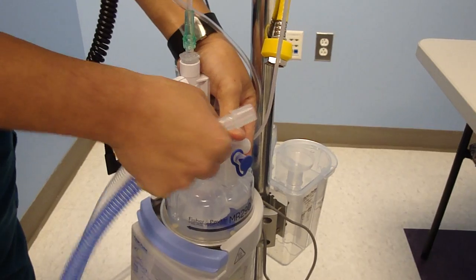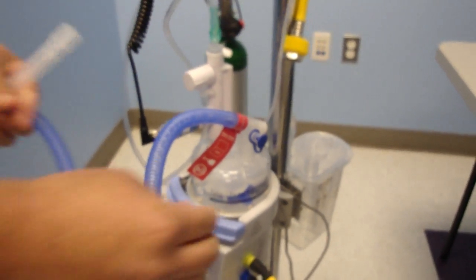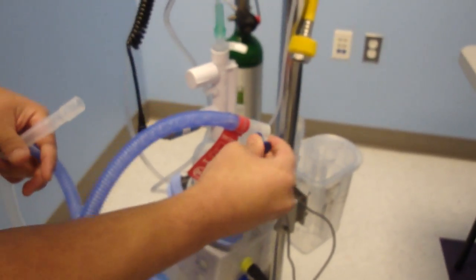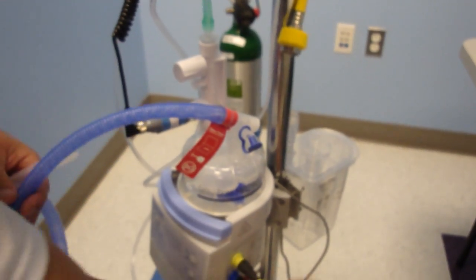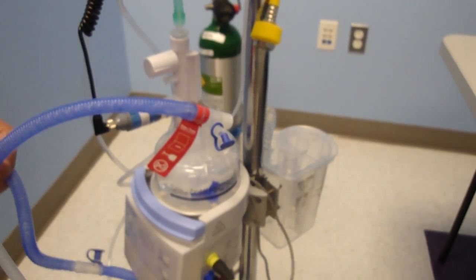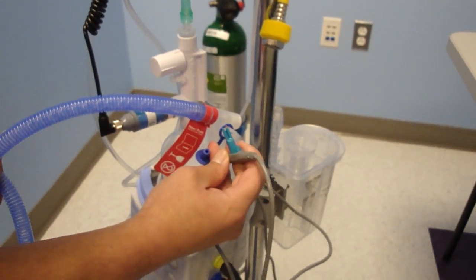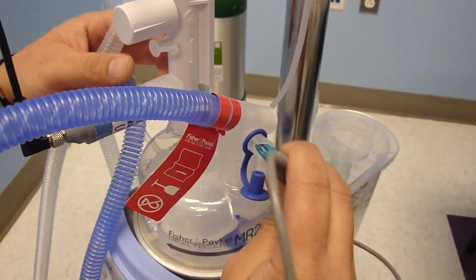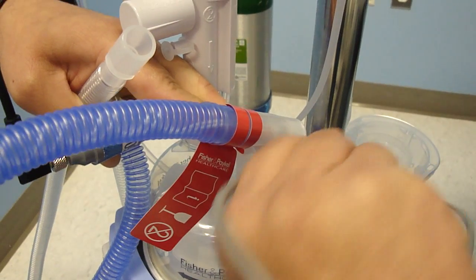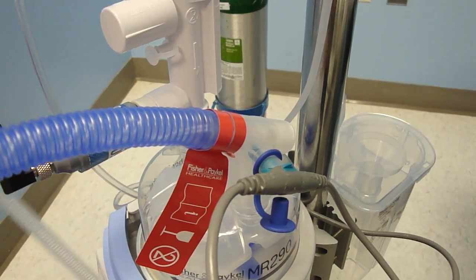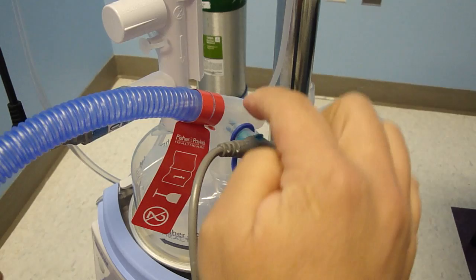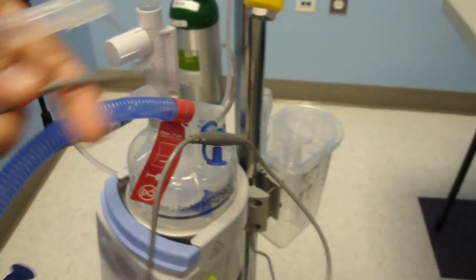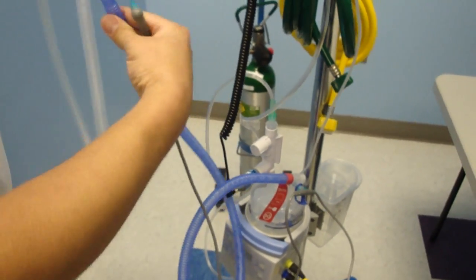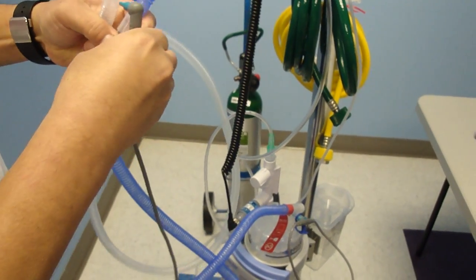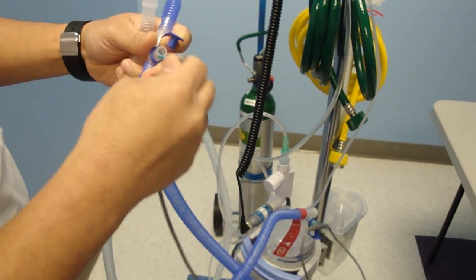Okay, so when you put it on the wet side, make sure your temperature probe is pushed all the way in to avoid additional condensation. See, the circuit has a V knot. You want to work it in as hard as you can until you're flush with the V, because that's very important, because that is the flow and the temperature probe built in. Okay, the other end, as long as you push it all the way in and you don't see any more blue, then you're good.